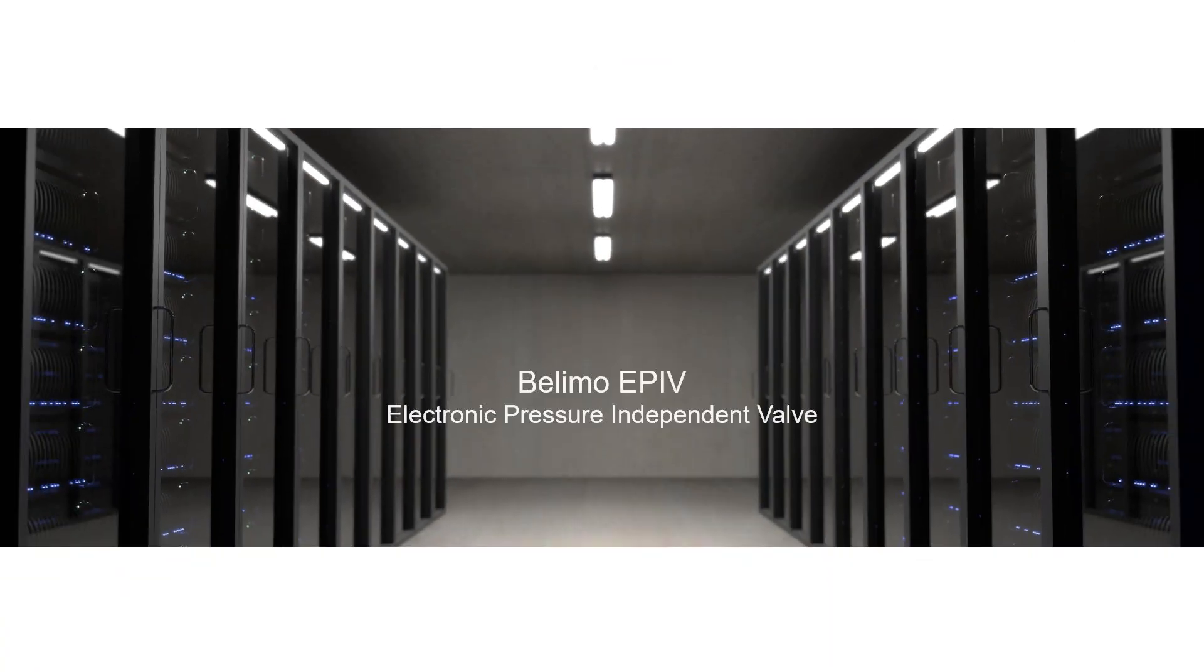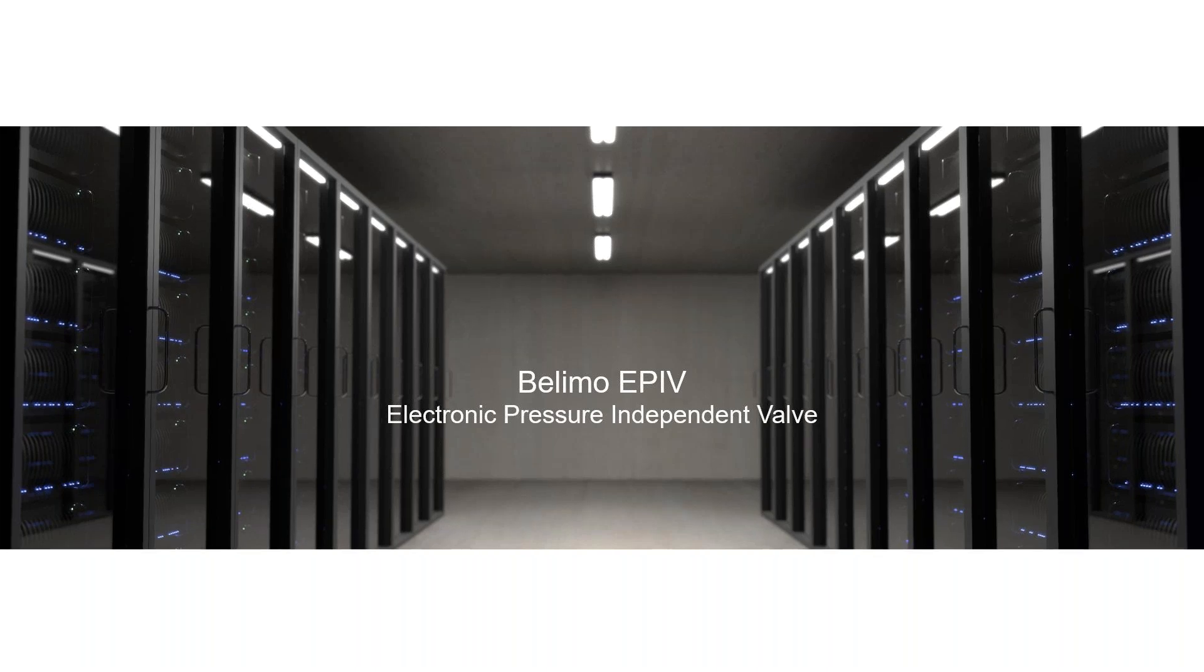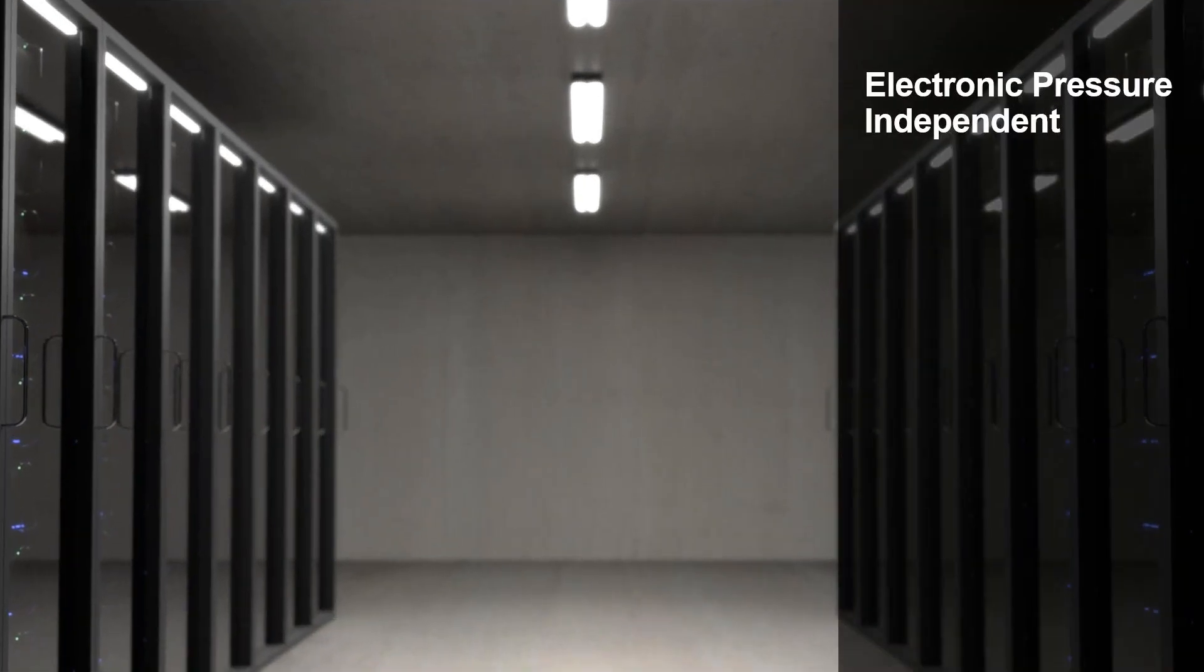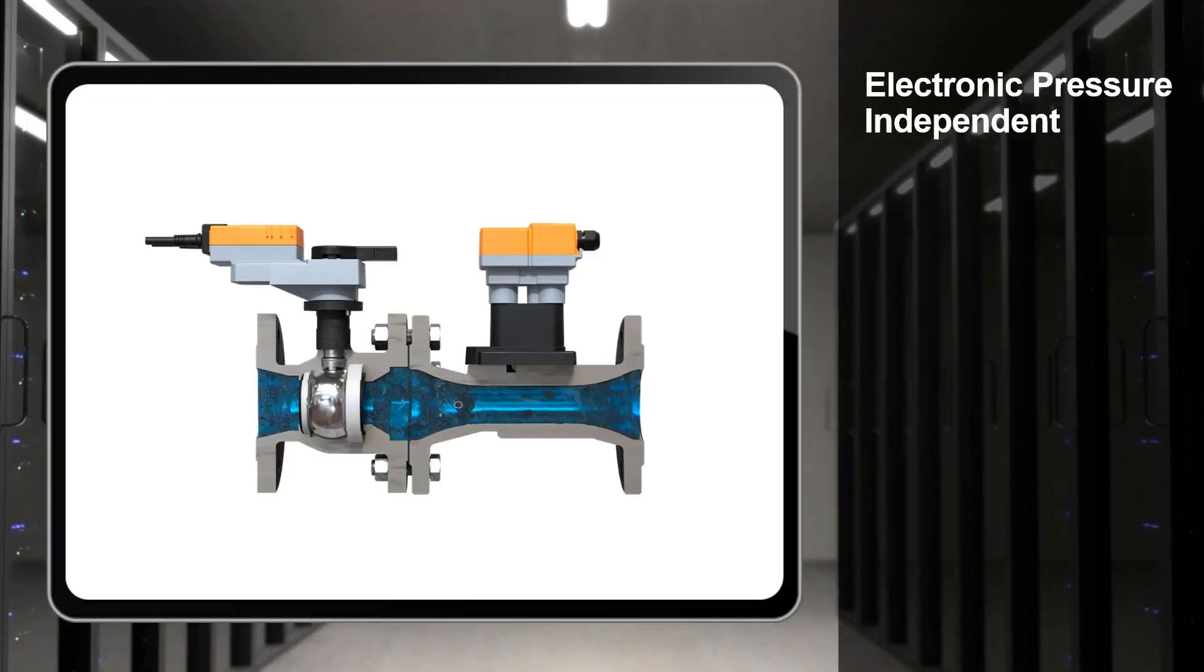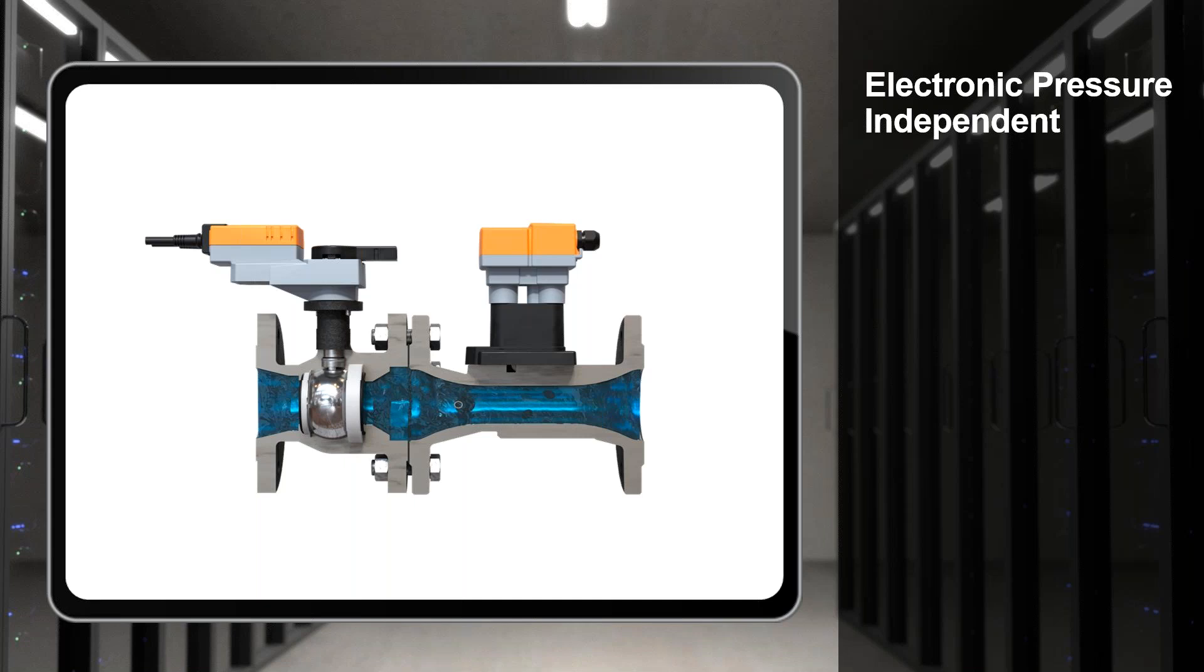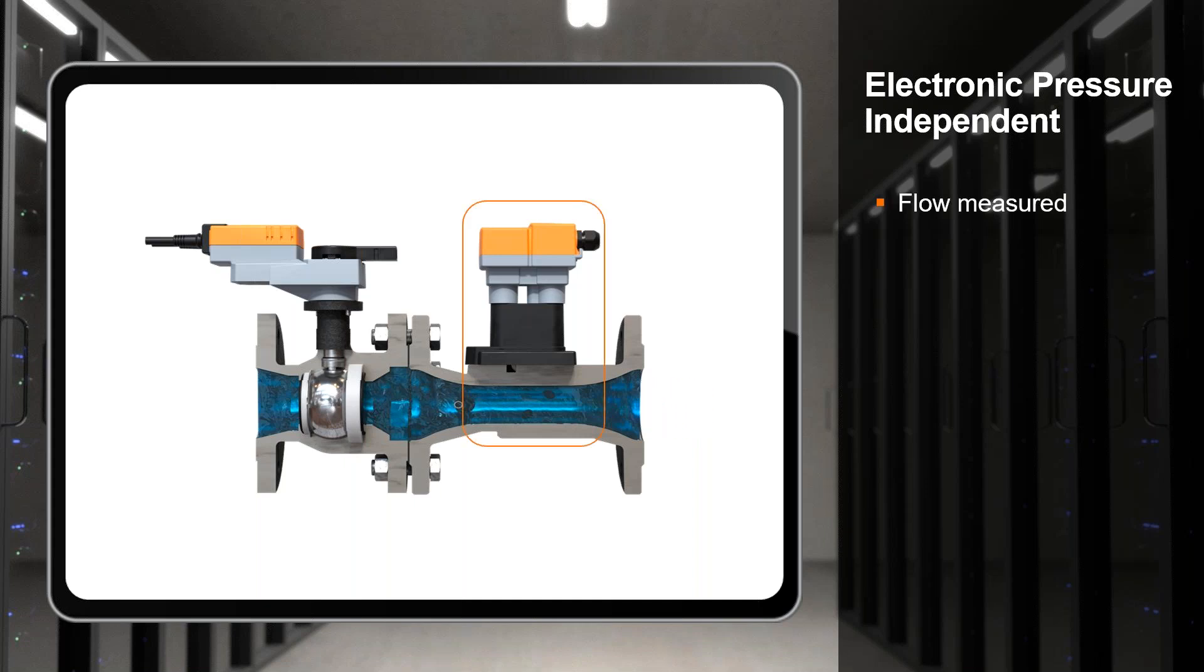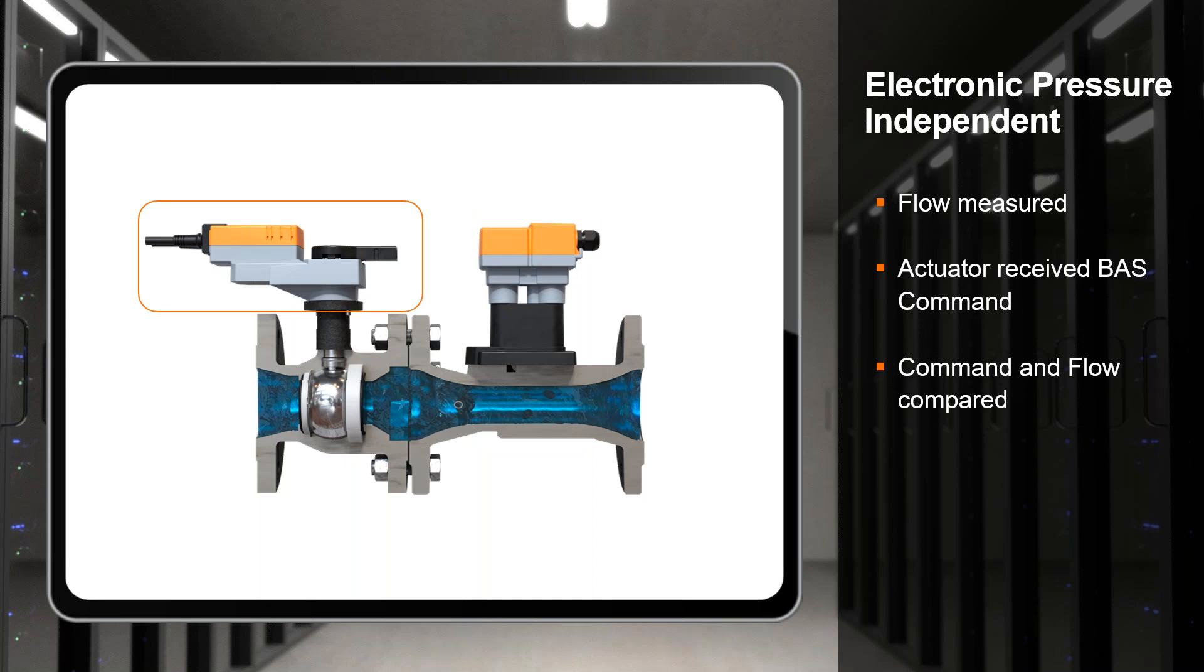We need the ability to be flexible, and this is where the Belimo EPIV shines. The EPIV stands for Electronic Pressure Independent Control Valve and it's a really clever device. If we take a look at this cutaway of a larger sized EPIV, what we're going to do is pass water through the valve. It's going to go through the flow meter which is on the right side there, and then through the control valve. This allows us to run a control logic not dissimilar to how a VAV box works in a standard HVAC application.